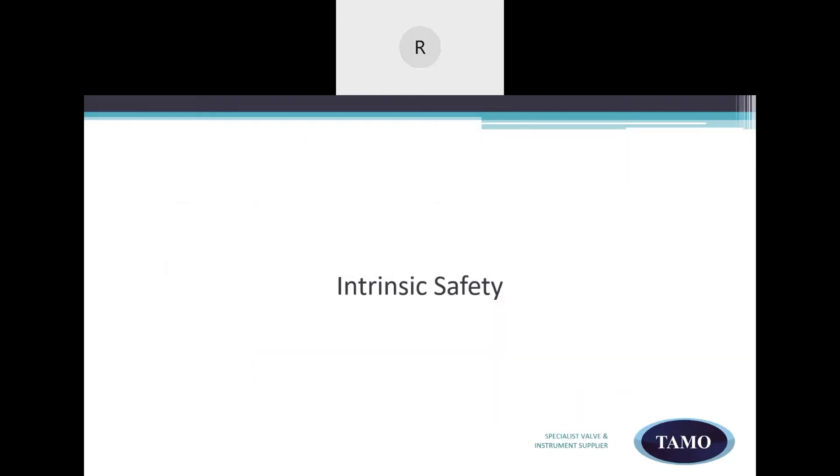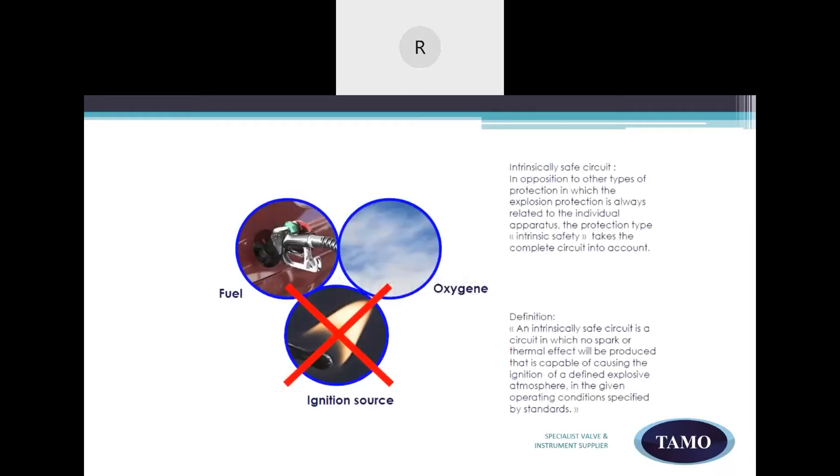Let's touch on intrinsic safety. An explosion requires fuel, oxygen and a source of ignition. Intrinsic safety removes the source of ignition. Let's look at the intrinsic safety protection technique and the definition of intrinsic safety. An intrinsically safe circuit is a circuit in which no spark or thermal effect will be produced that is capable of causing the ignition of a defined explosive atmosphere in the given operating conditions specified by standards. An intrinsically safe circuit, in opposition to other types of protection in which the explosion protection is always related to the individual apparatus, the protection type intrinsic safety takes the complete circuit into account.